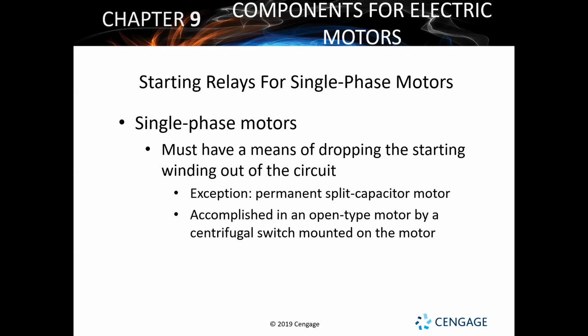That's the whole idea we have with things like a centrifugal switch, or with different temperature sensors and temperature relays that we can use, and things that are going to be sensitive to current level and all sorts of different ways that we can make sure we disconnect our start winding. Why do we need to disconnect our start winding? Well, because the start winding has more windings to it, which means it has more wires. That means it's going to be consuming more electricity, and it's going to draw higher amperage. We need that high energy and amperage when we're starting the motor to overcome that initial lockup that the motor has when it's sitting there still.